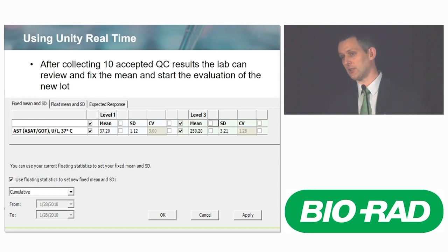What is also important, and I went over it a bit quickly in my overview slide, is that even when you have established a mean and copied over that standard deviation, throughout the next months it's good during your QC revisions or your QC reviews to go and evaluate those targets. Because everything we do with 10 points is an estimation. So it's always better, the more data we get, to review if we don't need to tweak that a little bit.